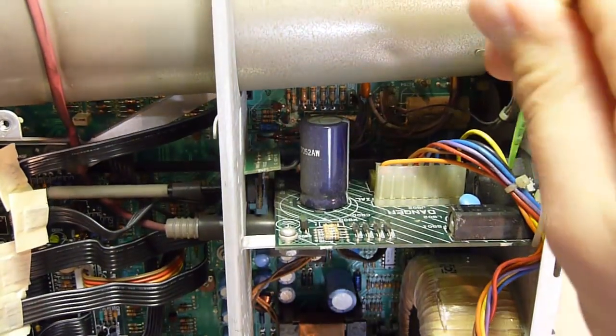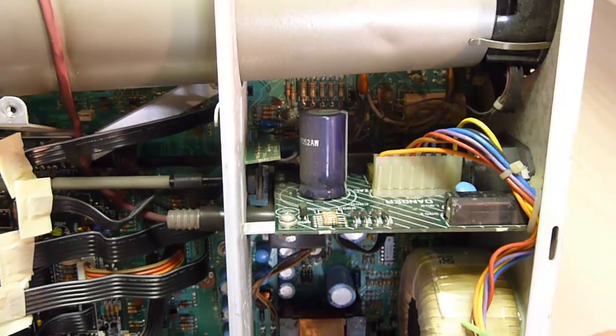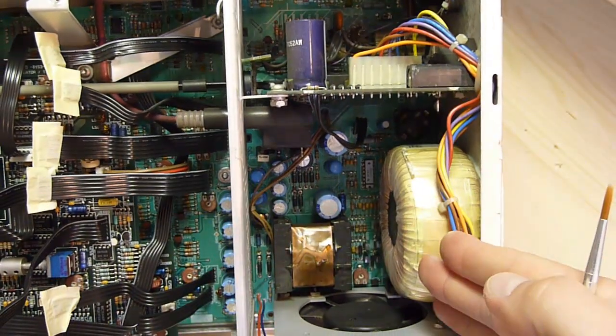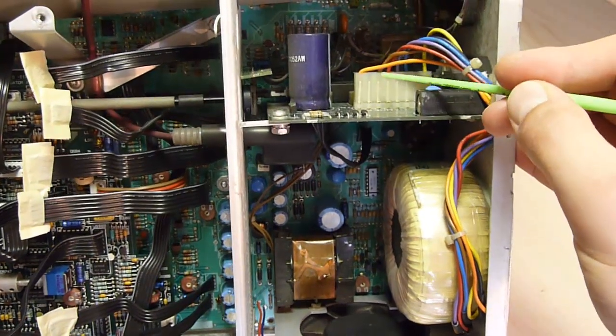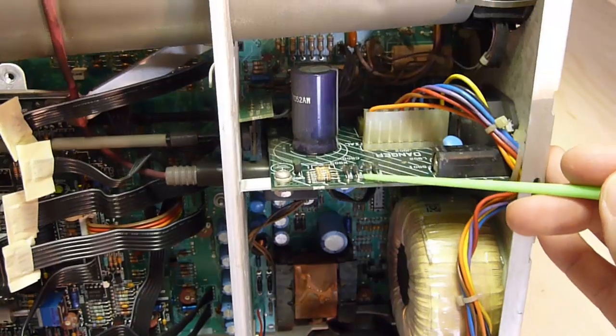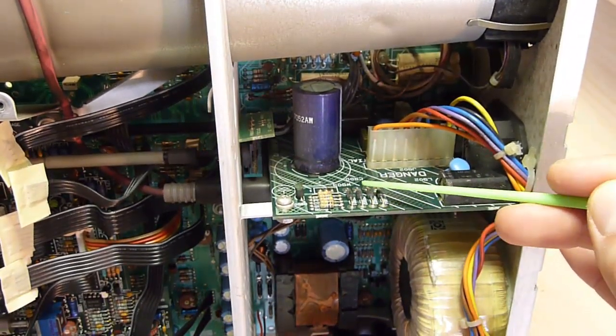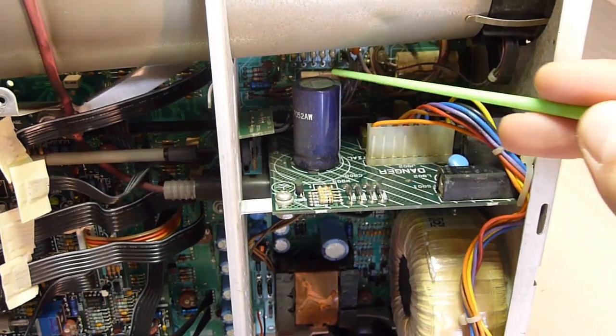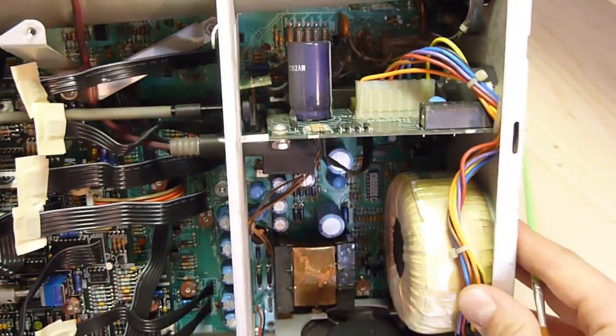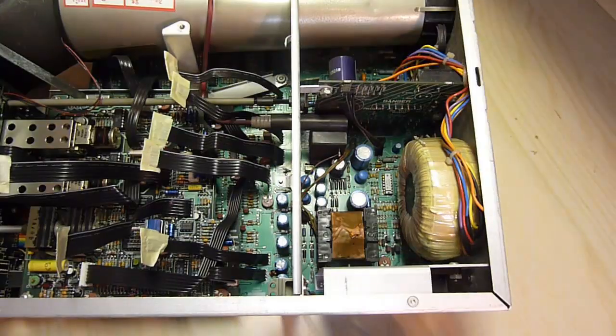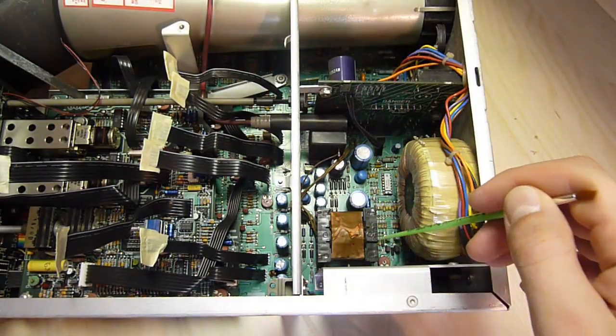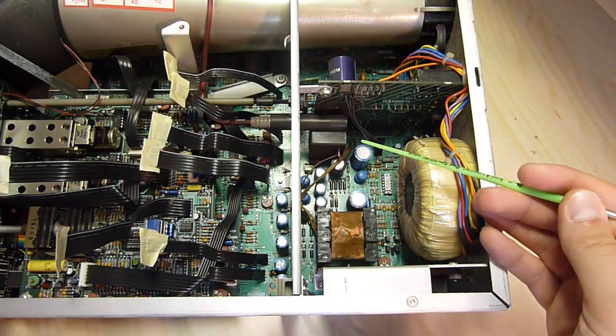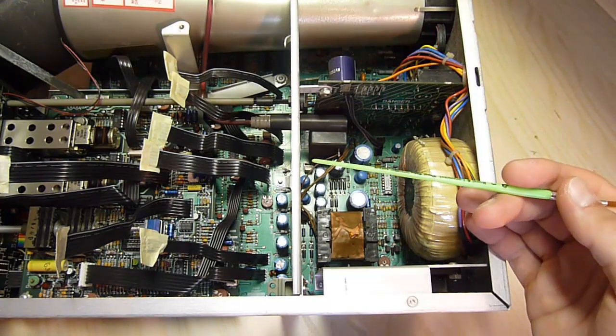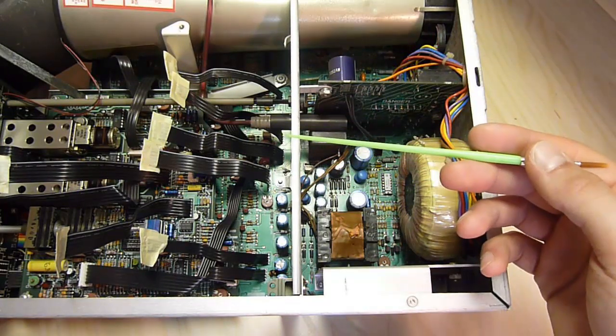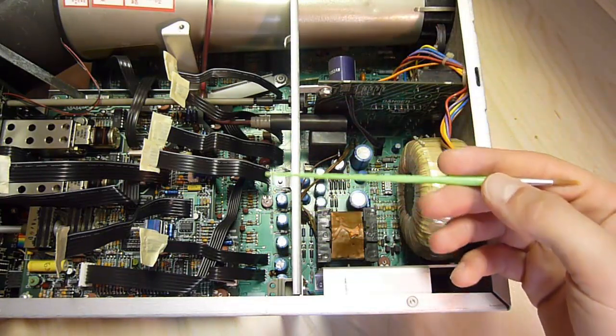So this is the IEC inlet, which goes into the main transformer over here, and from the main transformer back to the main input board, and we have a 4-diode rectifier and a filter capacitor, and from there the rectified voltage goes to the main power supply board. The switching power supply will generate all the various voltages that are required by all the circuitry, and it will then distribute all the voltages to all the boards.